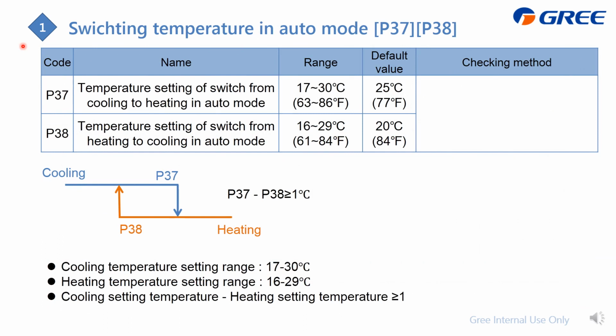Switch temperature setting in auto mode. P37 is for cooling to heating, and P38 is for heating to cooling. That means even in auto mode, we are allowed to set the switch temperature between cooling and heating. This can meet the customer's requirement.